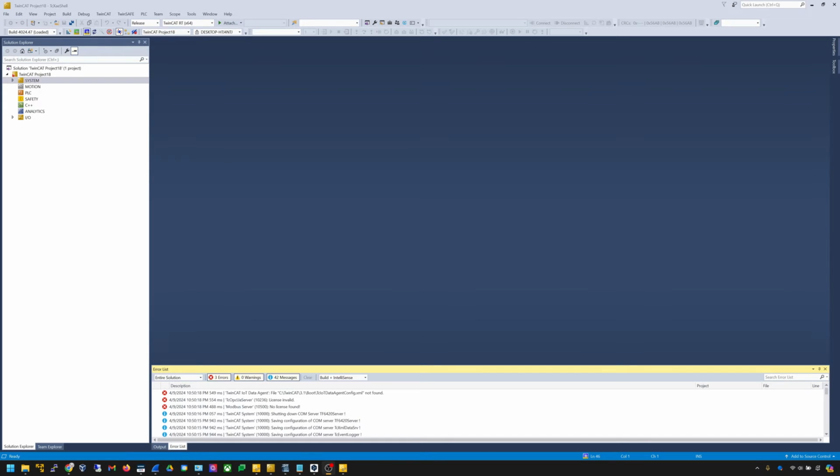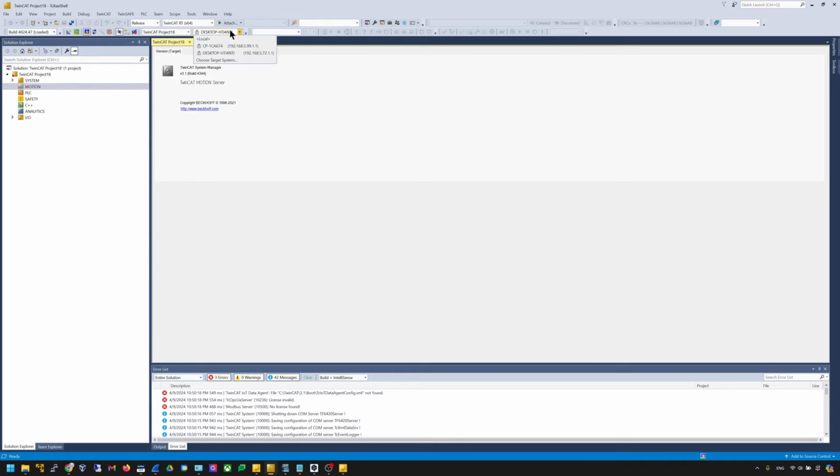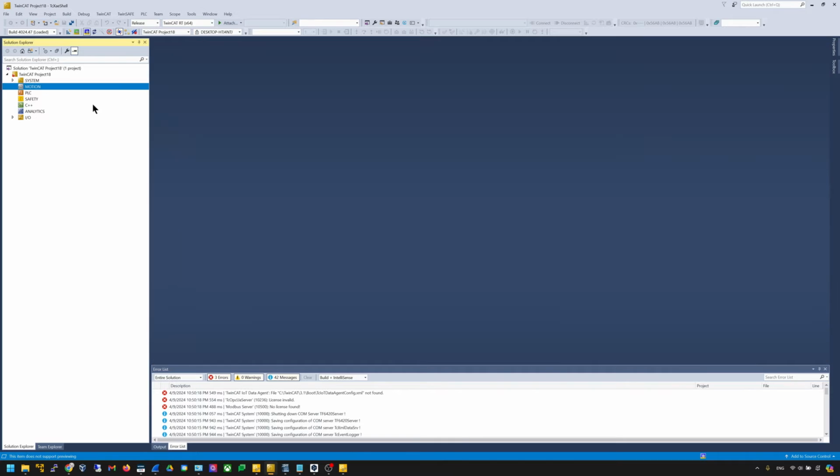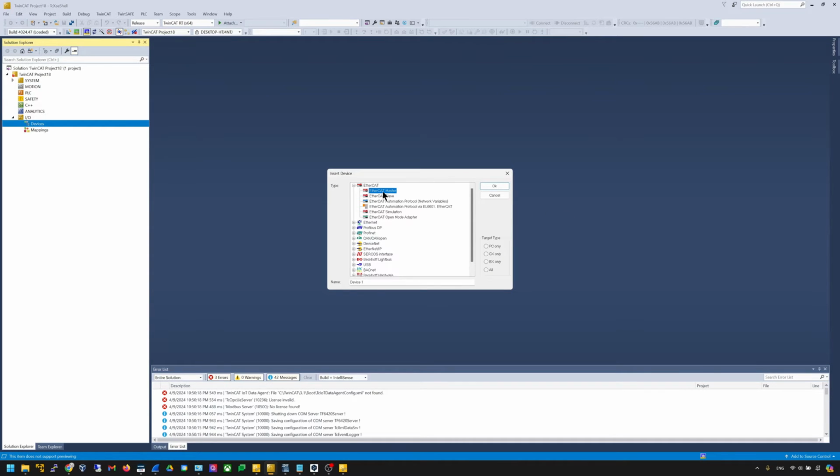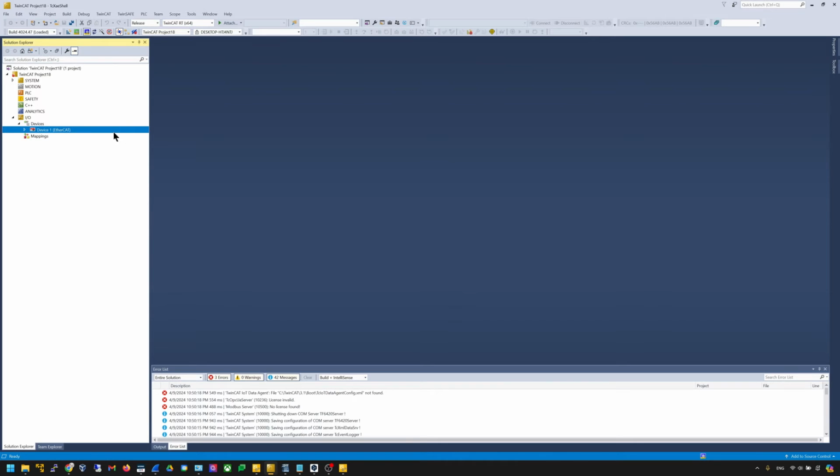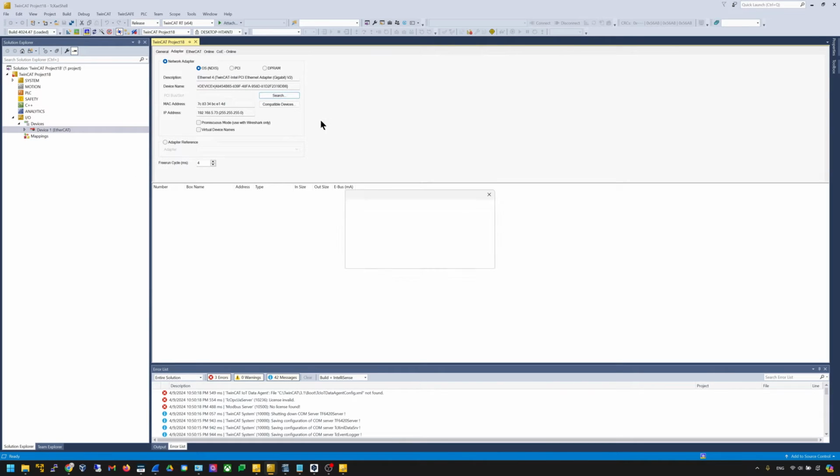Okay, now we start the TwinCAT project side. So what we need to do first, we need to confirm that you are connecting the right runtime here. So drop down here to select the right runtime, and then go to IO, EtherCAT, right click, add new items, choose EtherCAT Master, and then double click it to choose the interface you want to use.